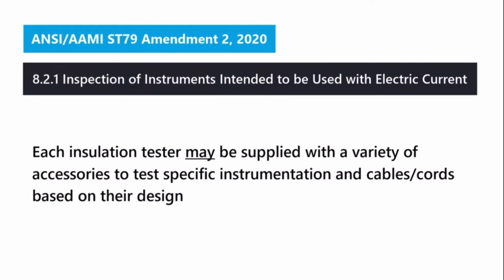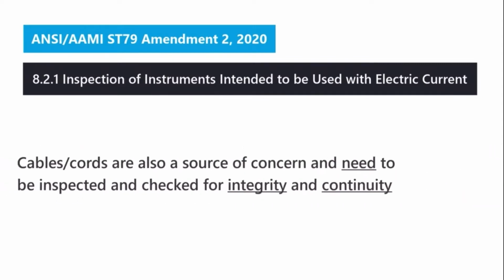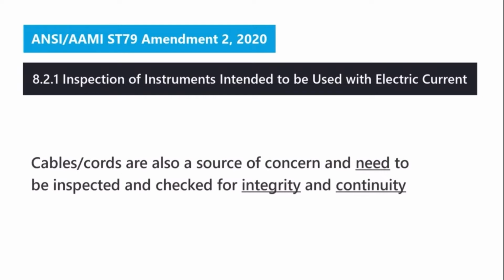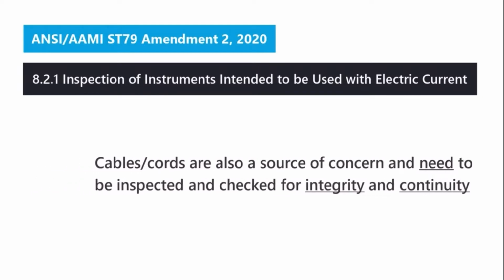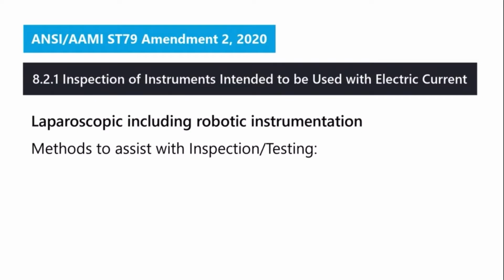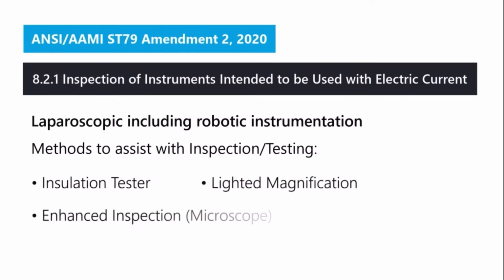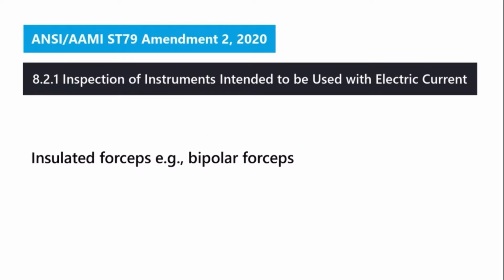Each insulation tester may be supplied with a variety of accessories to test specific instrumentation and cables/cords based on their design. Cables and cords are also a source of concern and need to be inspected and checked for integrity and continuity. Also included in the document is a table/list that states laparoscopic, including robotic instrumentation. Methods to assist with inspection/testing are as follows: insulation tester, lighted magnification, enhanced inspection microscope, visual inspection, and tactile inspection. Also included in the list is insulated forceps, example bipolar forceps.